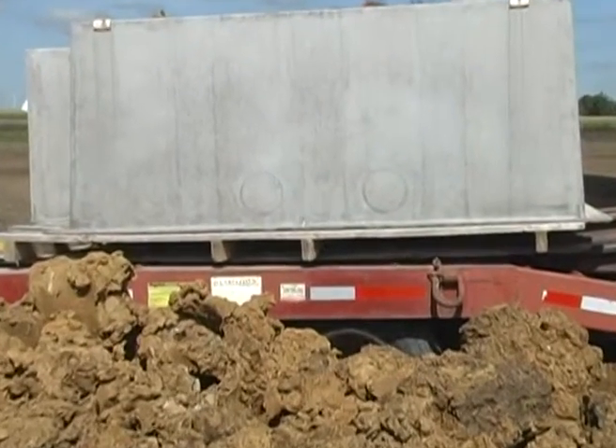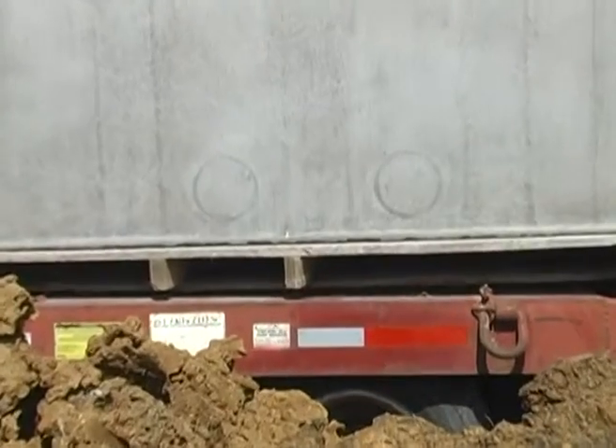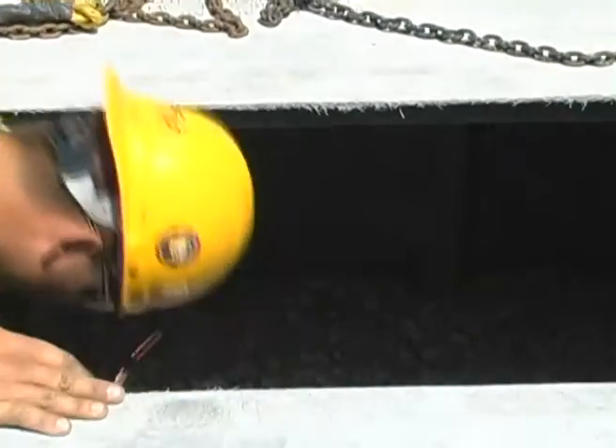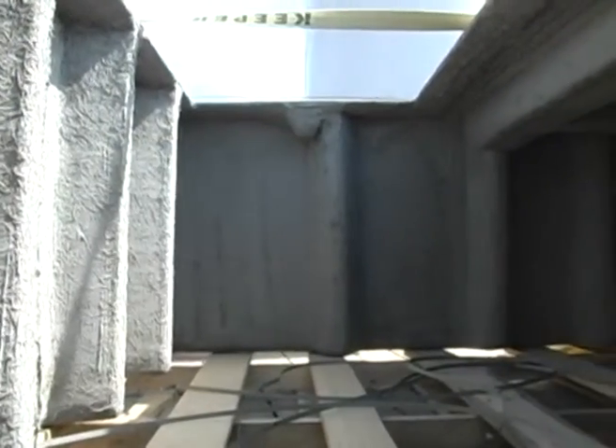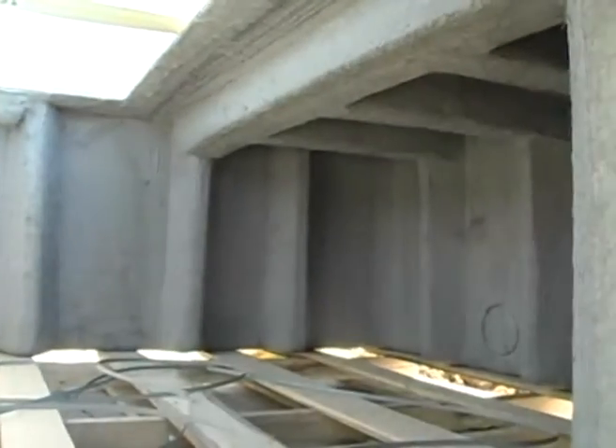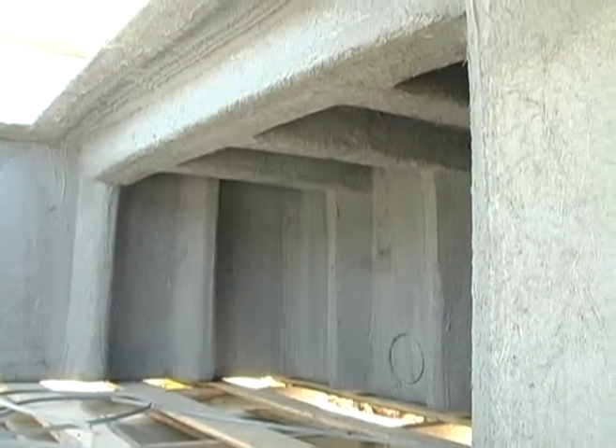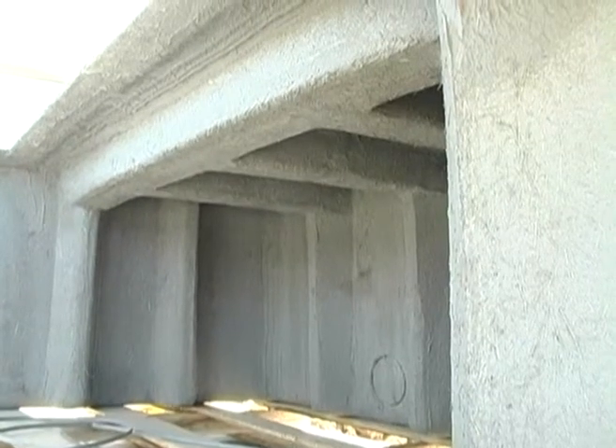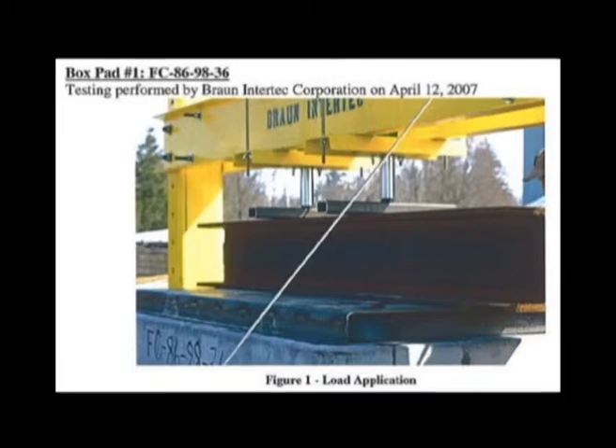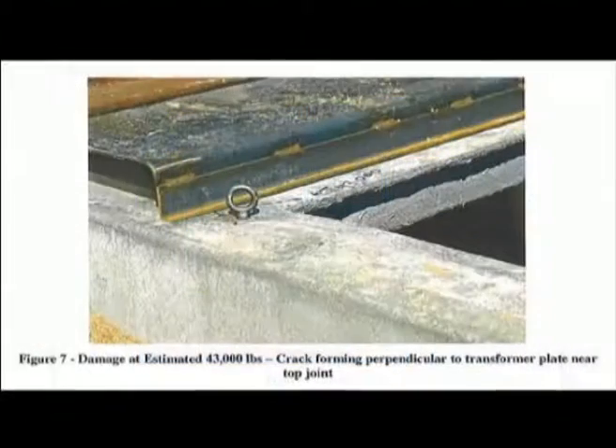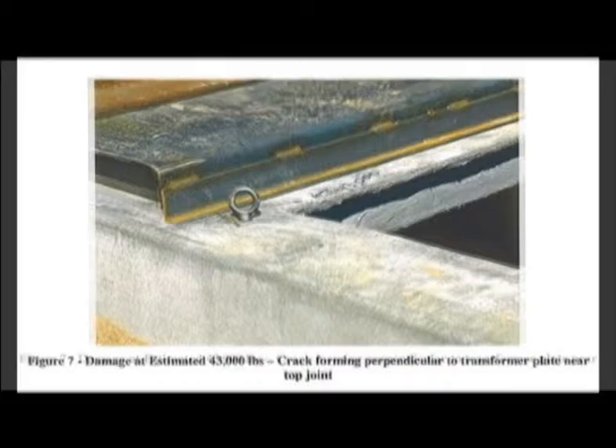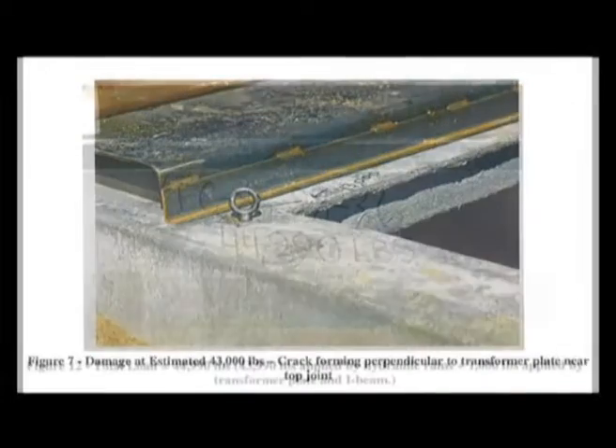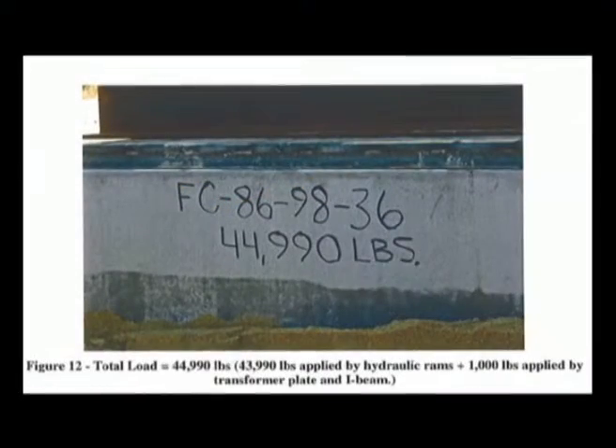Knockouts are inserted into the walls for cable entry and exit through a section of conduit. A generous number of ribs are built into the walls and the top of the pad to provide outstanding load distribution for the stability of the heavy 3-phase transformer. This transformer-based design has been tested to a loading of over 40,000 pounds, which allows for plenty of safety factor to meet the installation and operation criteria.